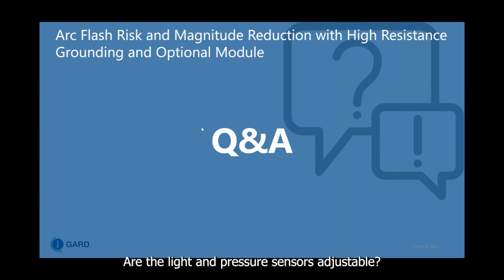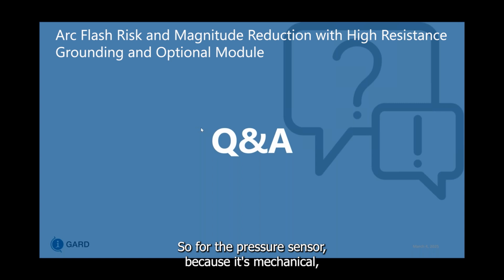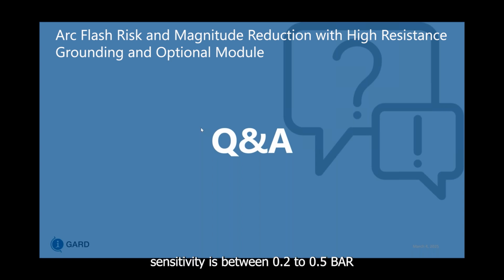Are the light and pressure sensors adjustable? They are not adjustable. For the pressure sensor, because it's mechanical, it's going to act a little bit slower at around 10 milliseconds, versus the light sensor, which is strictly electrical and light based with fiber optics, which is our fastest solution. Now, the pressure sensor's sensitivity is between 0.2 to 0.5 BAR.